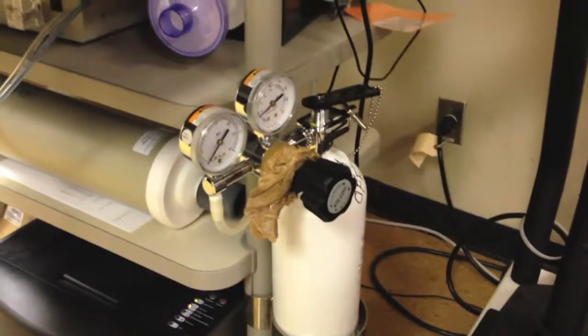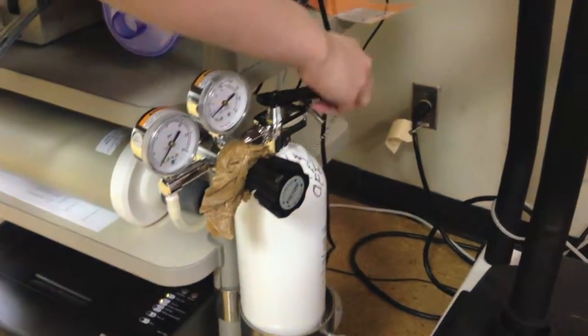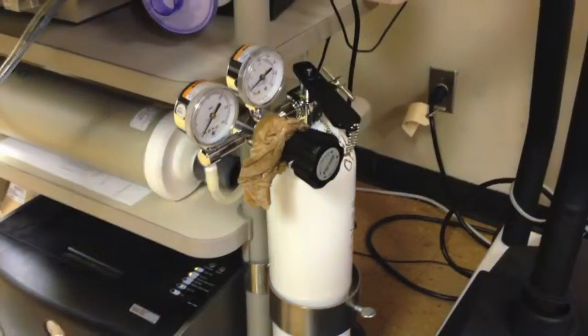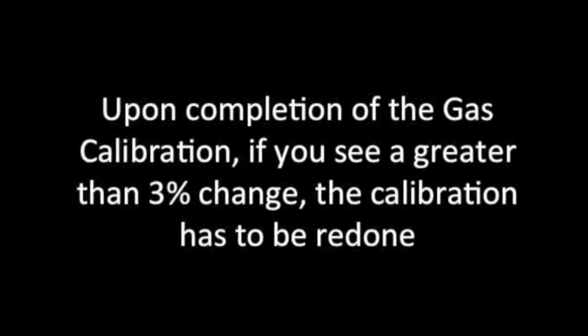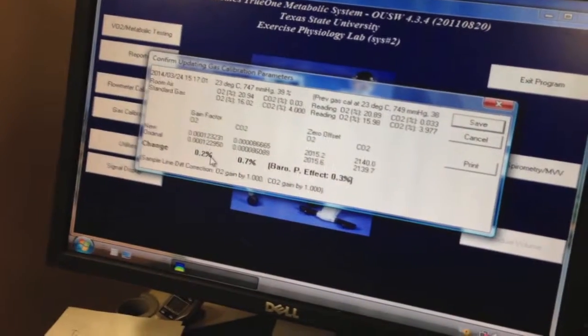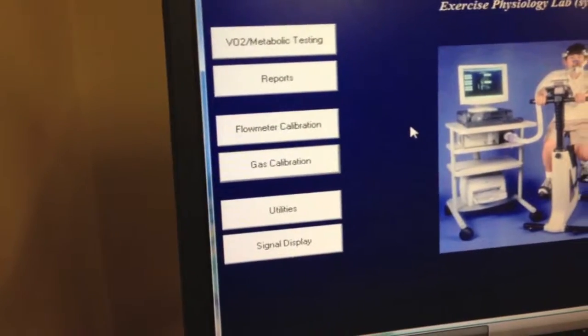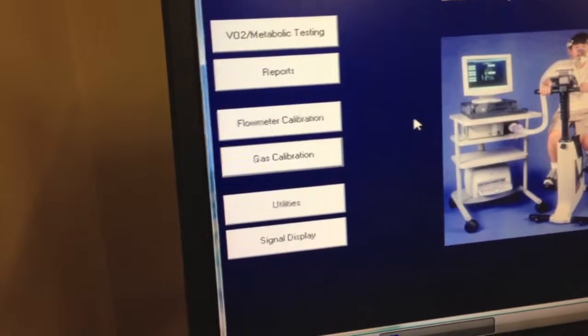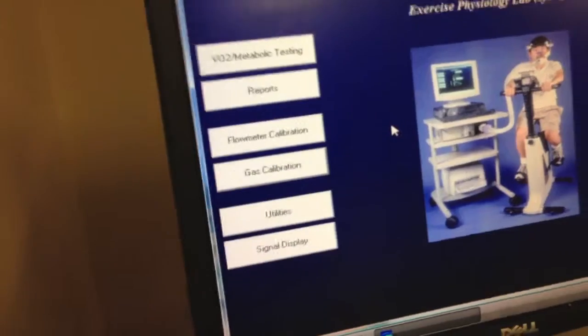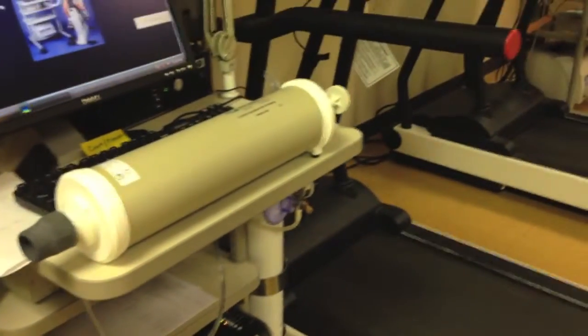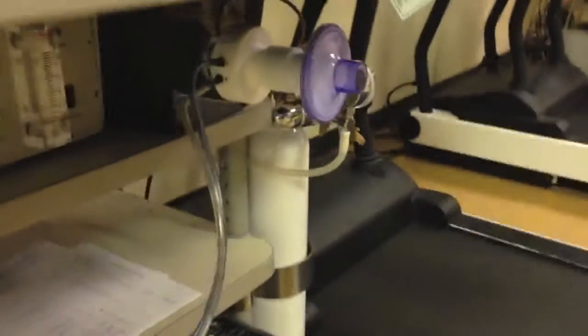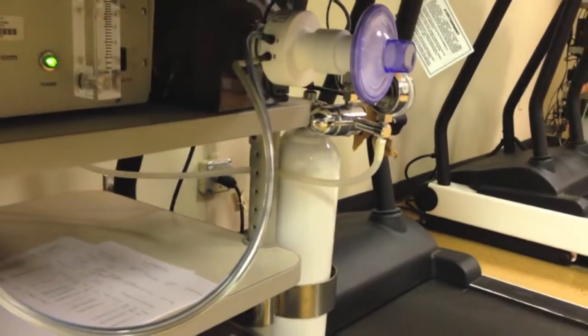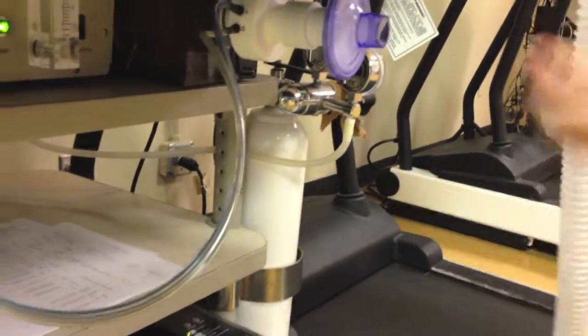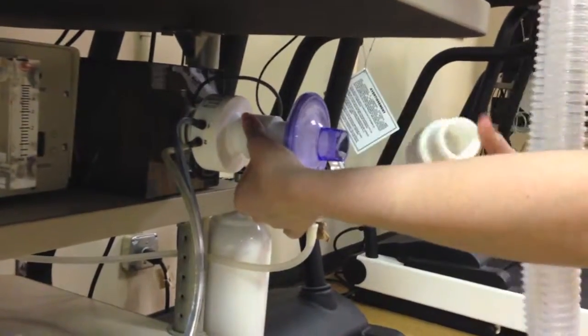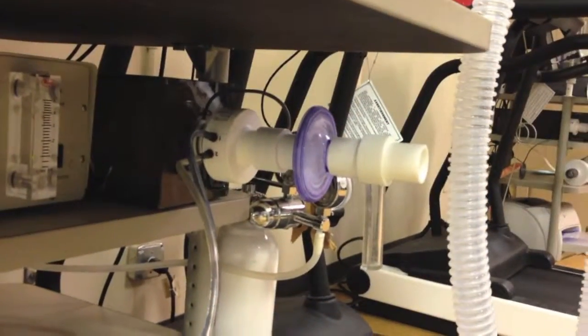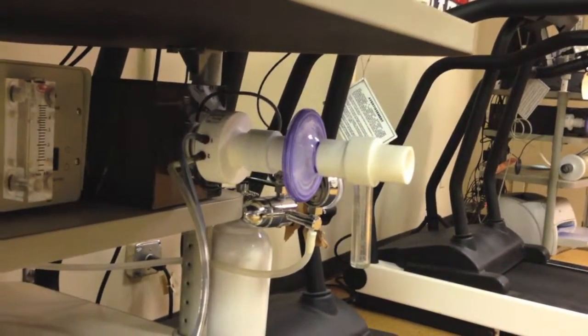After the computer's finished sampling the air, you'll go back to the gas tank and turn it clockwise another 90 degrees to turn it off. The next step is flow meter calibration, which will immediately follow gas calibration. First, make sure that all of the necessary equipment is set up correctly. You'll have a moisture filter connected to a liquid trap.